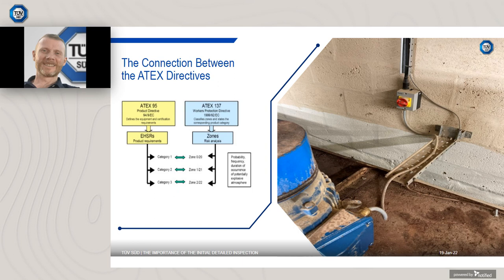The installation in the photograph is a good example of the levels of EX protection required for a specific zone. The factory had, after being made aware of zoning requirements in an extraction system, replaced non-certified fans and motors with certified units. No attention had been paid to the non-certified isolators located within the zoned areas. Reliance was left upon an installer without the correct knowledge base to carry out the work.